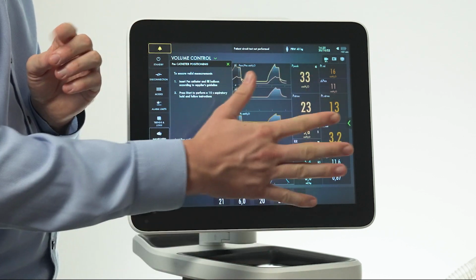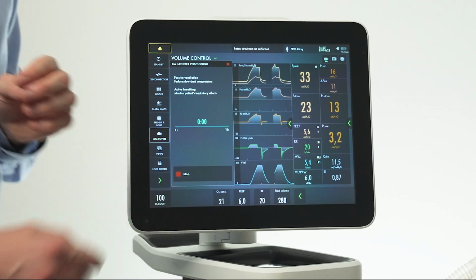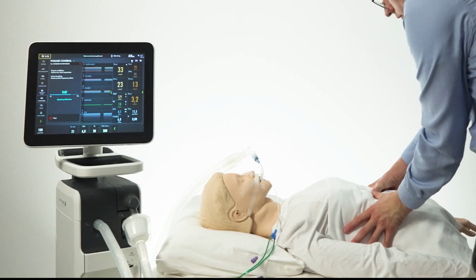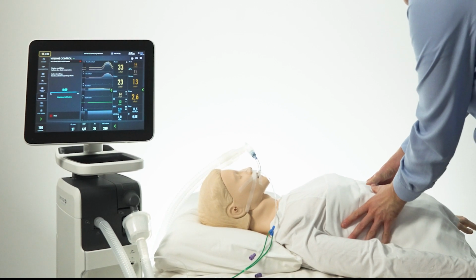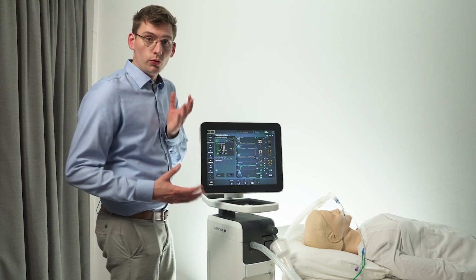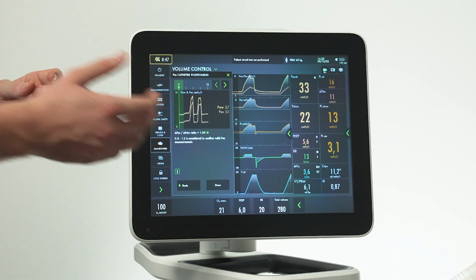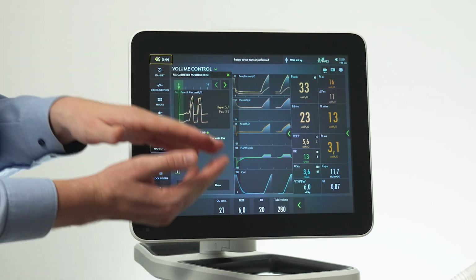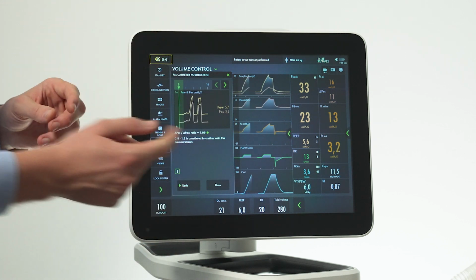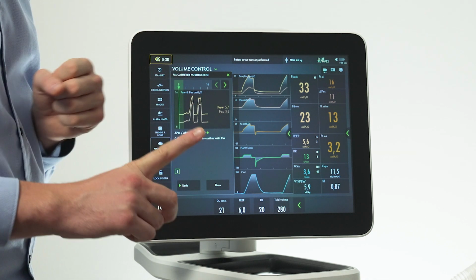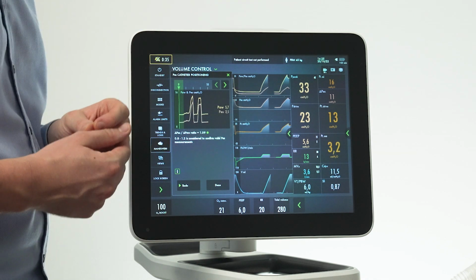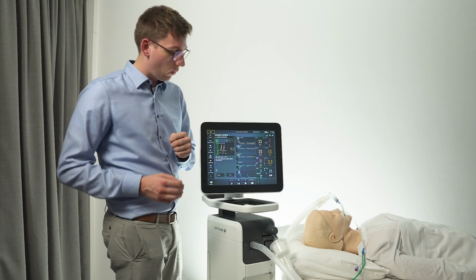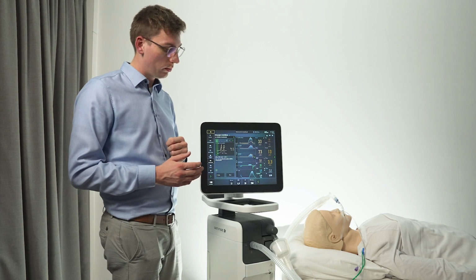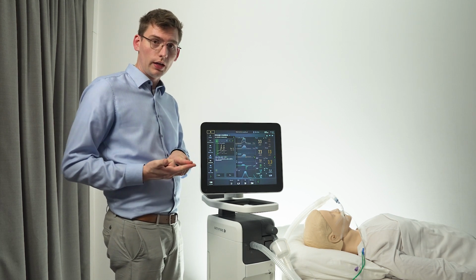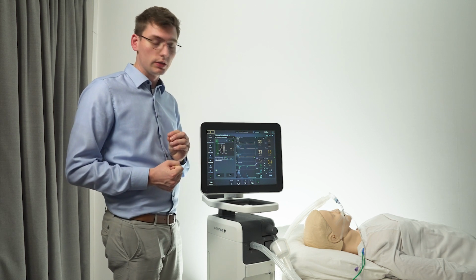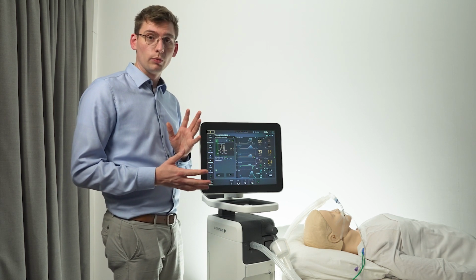And in these 10 seconds, you have to do your thoracic compression. I press start, I walk over to my patient, place both hands on both sides of the thorax, press down on the thorax once, release, twice, release. The tool has calculated the ratio for us, and it shows that the ratio between the rise in esophageal pressure and airway pressure is 1.09. We want this ratio to be between 0.8 and 1.2, and as close to 1 as possible. So 1.09 is very acceptable. And what that ratio means is that now we know the balloon is at the adequate position and filling, and we can use the esophageal pressure readings to conduct reliable measurements in our patient now.